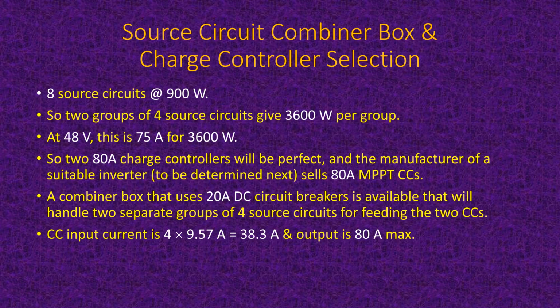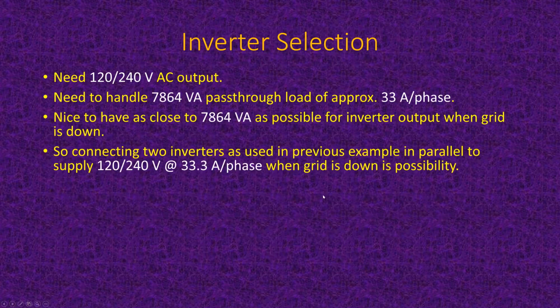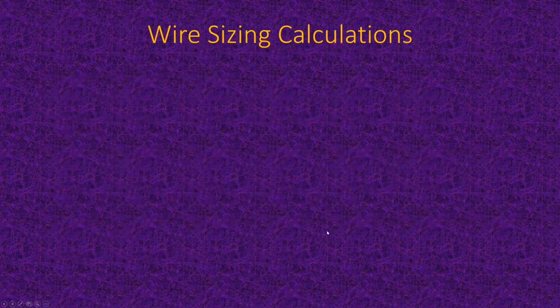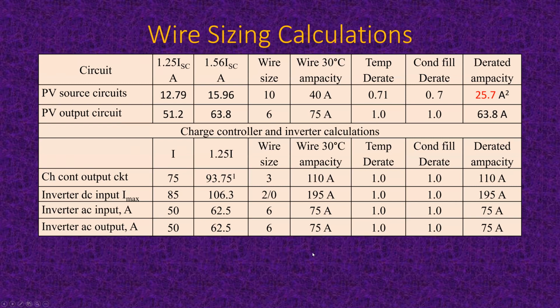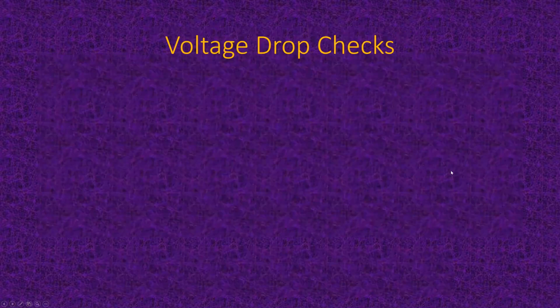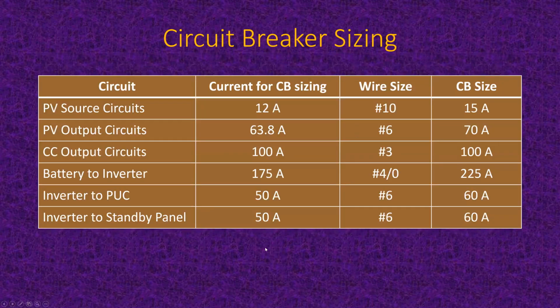And then a combiner box to combine the outputs of these circuits. And usually they use 20 amp circuit breakers, sometimes 20 amp fuses, but mostly DC circuit breakers now. So again, here's the inverter. Again, same story. Same story for calculating wire sizes. Again, we're still using number 10 on the source circuits, but now for the output circuit, it's a lot more current, it's twice as much. Okay. And check the voltage drops. Again, same sort of thing. Size the circuit breakers, and here's the typical circuit breakers you'd be using on that particular system.